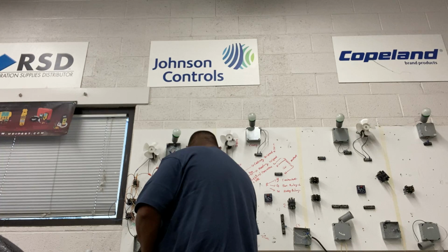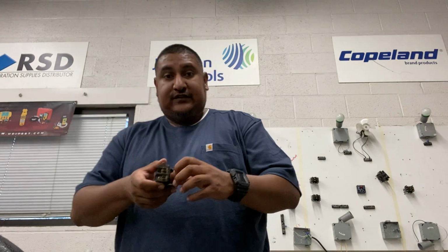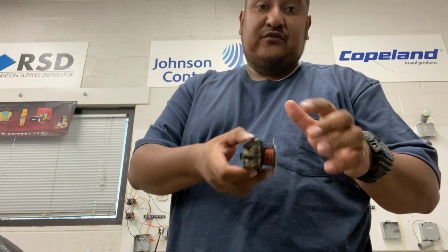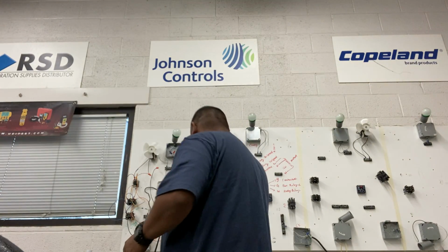And just like I told you a few minutes ago, this coil for this contactor operates on 24 volts. Now, what you have to understand is you have two types of voltages in any type of system. You have your working voltage, the stuff that's going to turn motors and compressors. Big power, 208 volts to 460 volts, depending on the system. And then you have small voltage, control voltage. This control voltage is just like the name implies. It's going to control the equipment.